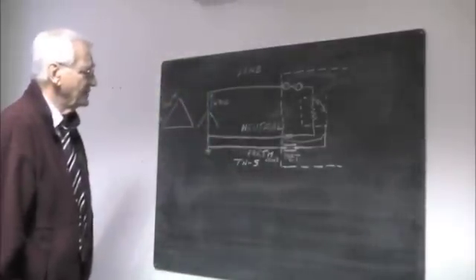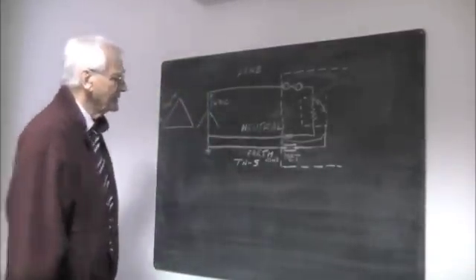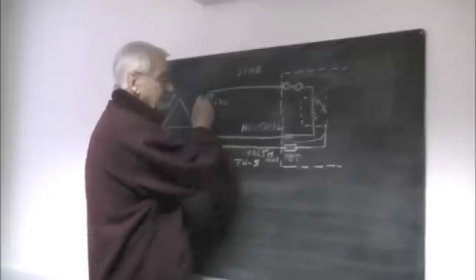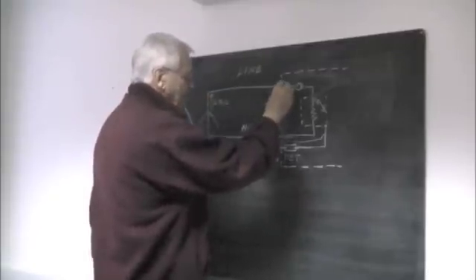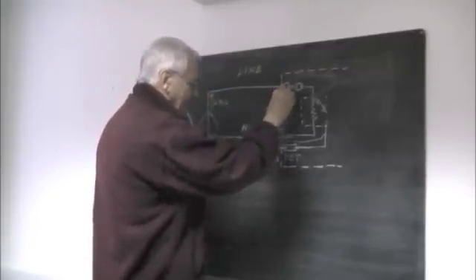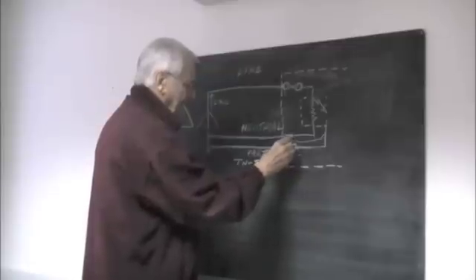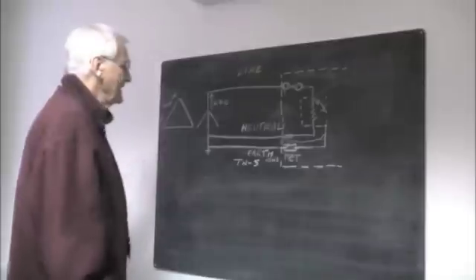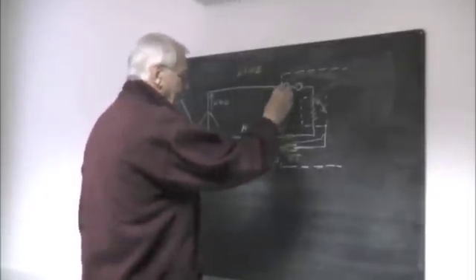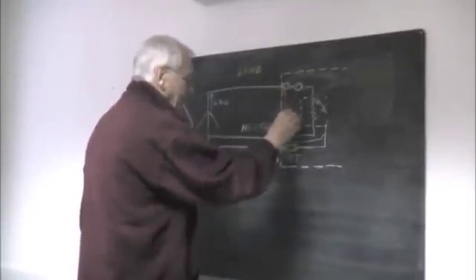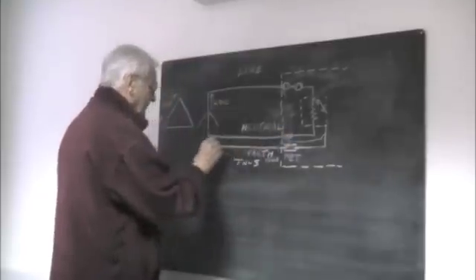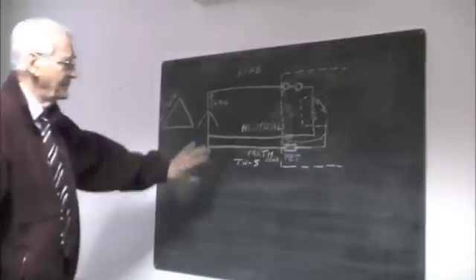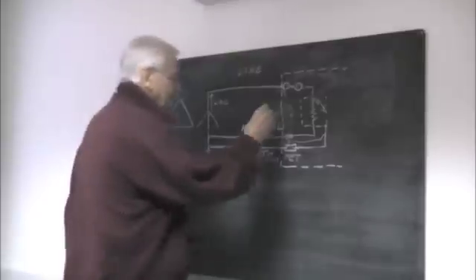Right, now let's just remind you how to do a ZE measurement first. We're going to actually measure the impedance of the loop as I've already explained to you, but in this case we're going to measure it from here to here, the MET, the earth. Those two points are just there, from there to there. And that's the ZE. So that loop will be through a resistance or a fault here, down here, through here, through here, around that way there. And that is measuring the loop impedance external to the building, hence ZE.